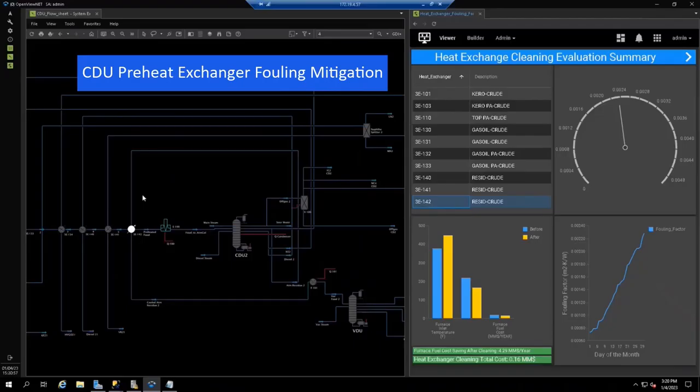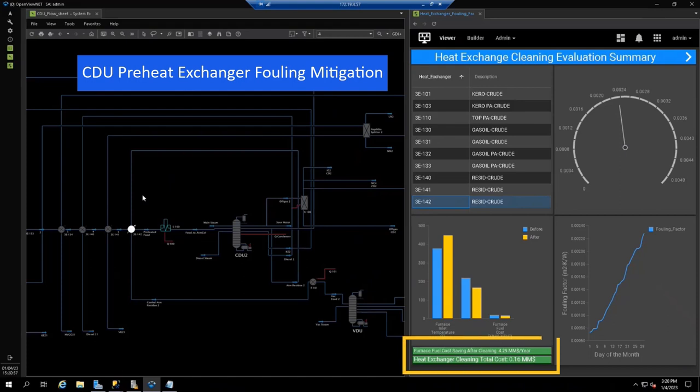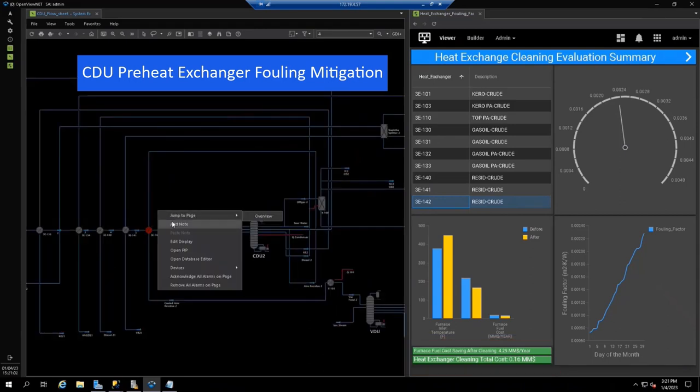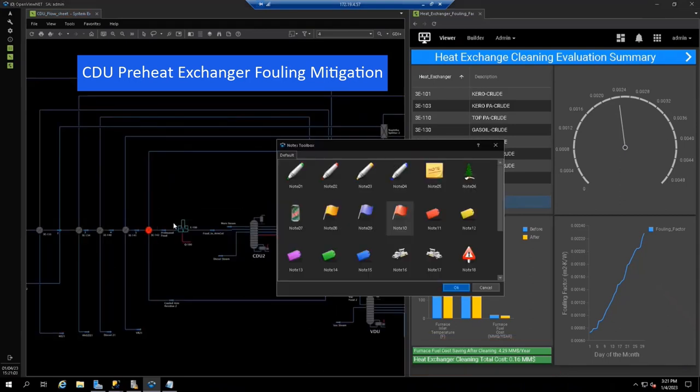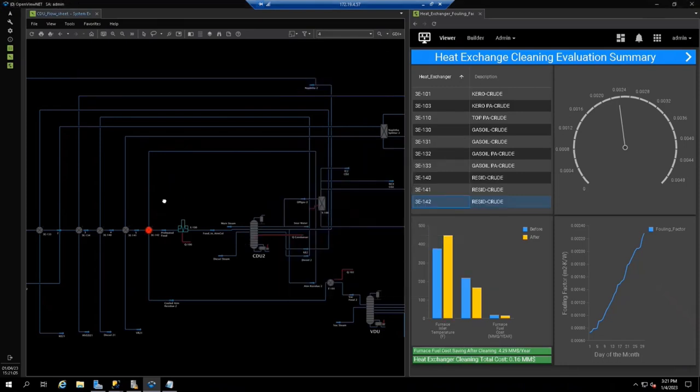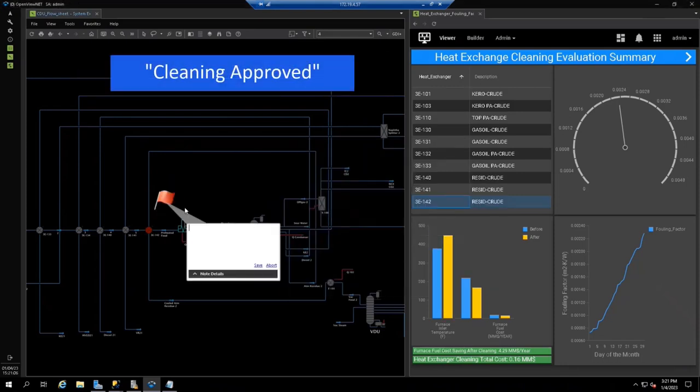Sure enough, one of the heat exchangers is at a threshold, meaning reduced efficiency, excess fuel consumption, and higher CO2 emissions. The heat exchanger model runs an economic analysis showing that with a cleaning cost of $160,000, it is possible to save $4.3 million a year while reducing carbon emissions. With a collaboration feature built into AspenTech's operational insights, we can quickly communicate the recommendation to others and set a target date for heat exchanger cleaning that will reduce carbon emissions.